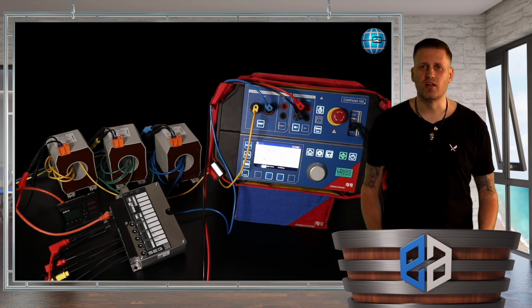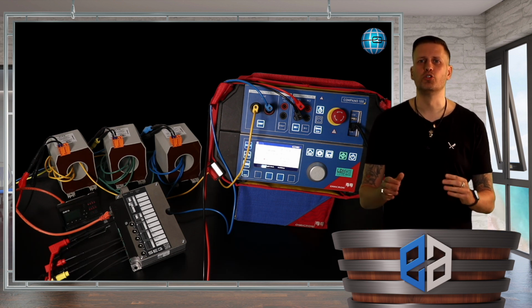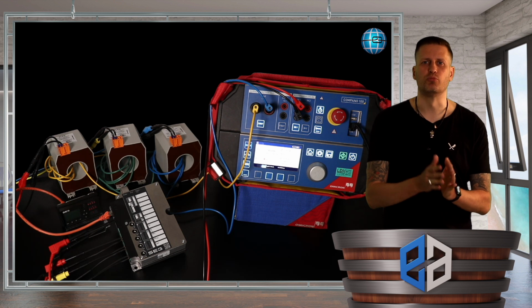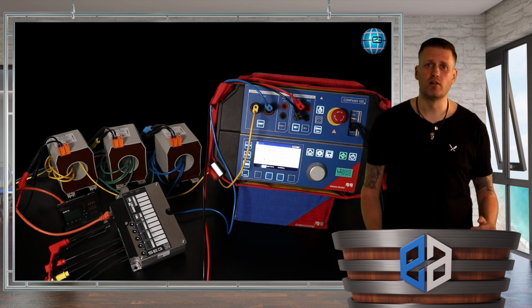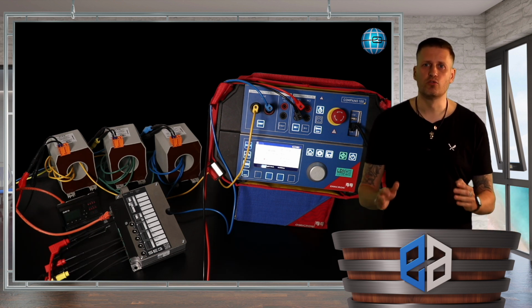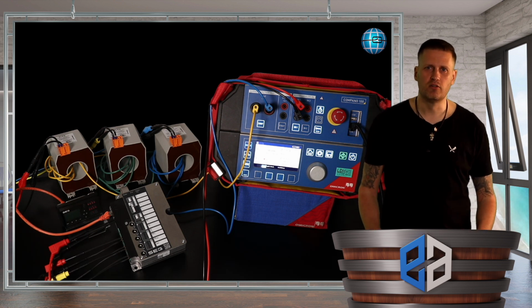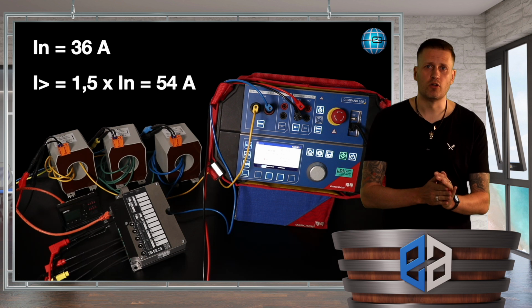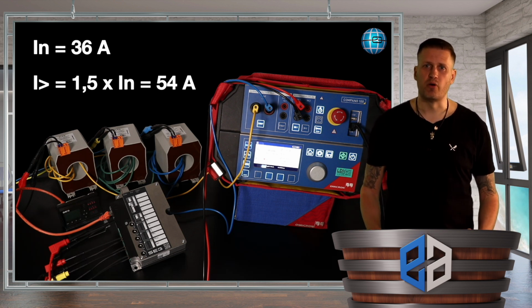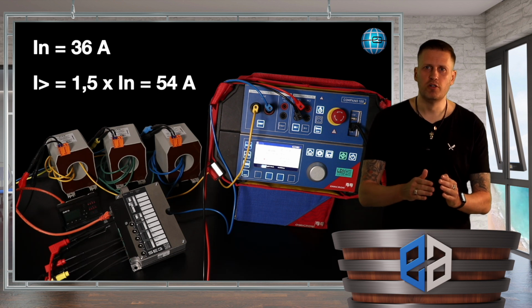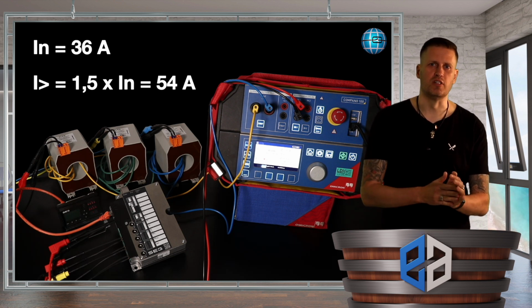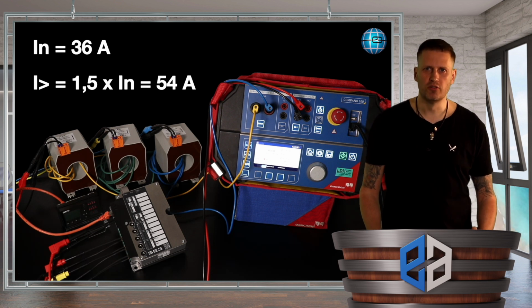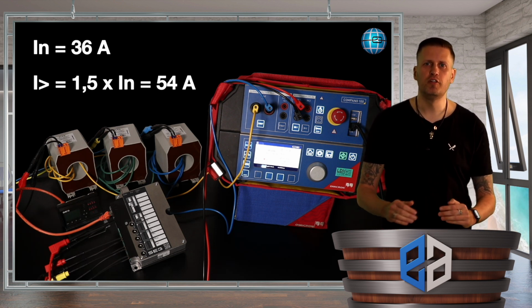but we want to get as close as possible to the conditions in practice and have decided to use a primary current injection. The trip signal of the WIC1 will be triggered via binary input 1 of the Compano, and we can also see the new DigiMac, which is connected to the WIC1 via Ethernet cable. Let's look at the settings. Our system configuration has a nominal current of 36 amps and we have parameterized a simple definite time value to 1.5 times the nominal current, which corresponds to a setting value of 54 amps.